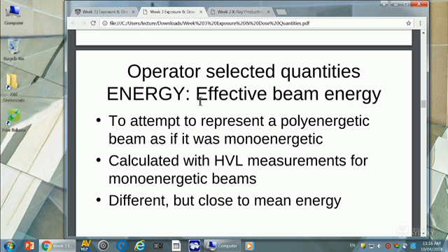If it's 73, you might need 2.41 millimeters of aluminium equivalent. If you've got 83, you might need 2.73 aluminium equivalent. And they have it all worked out. These people who can produce monoenergetic beams have it all worked out. Okay, that's the first step to this.